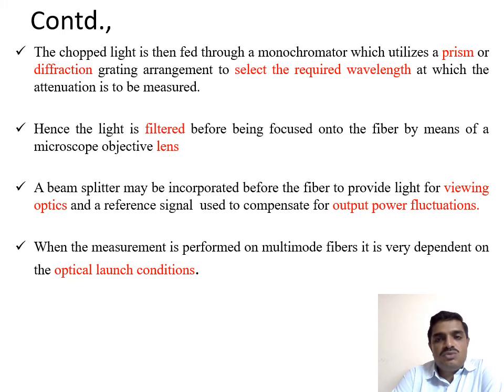The chopped light is fed through a monochromator, which utilizes a prism or diffraction grating arrangement to select the required wavelength at which attenuation is to be measured. The light is filtered before being focused onto the fiber by means of a microscope objective lens. A beam splitter may be incorporated before the fiber to provide light for viewing optics and a reference signal used to compensate for output power fluctuations. When measurement is performed on multimode fibers, it is very dependent on optical launch conditions.